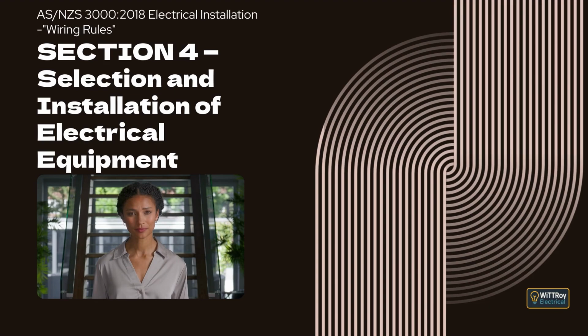Clause 4.20.2 Lift supply arrangement. Each lift must be supplied by a dedicated circuit to ensure reliable and identifiable electrical supply. Clause 4.20.3 Labeling. Lift circuits must be clearly identified by contrasting coloring or other suitable means so that they are recognizable and not inadvertently switched off. Clause 4.20.4 Motor room-less lifts. Clause 4.20.4.1 General. Motor room-less lifts are lifts designed without a traditional lift motor room, and where installed as emergency lifts they must also comply with the additional safety service requirements.